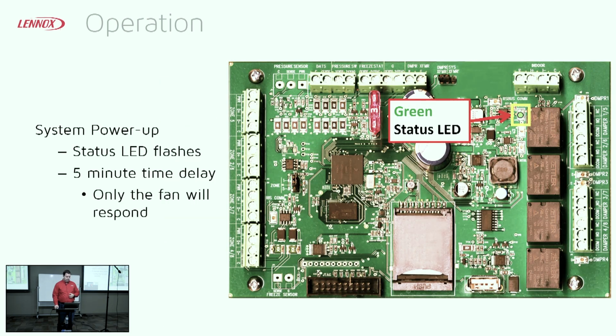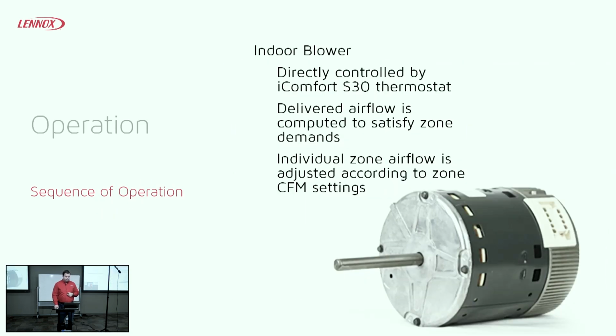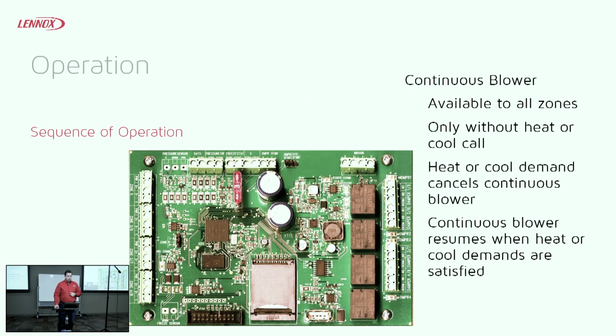Okay, coming down towards the end here. So again, basic is going to be your 5-minute delay, or your green status light if everything's working. Usually that's the only thing that's going to be on. You've got the 5-minute time delay built into it. As far as your sequence of operations, continuous blower is going to work only when everything's idle, because obviously if we're getting a heating or cooling call, it's going to close off to an individual zone, but you can set that CFM for each individual zone.